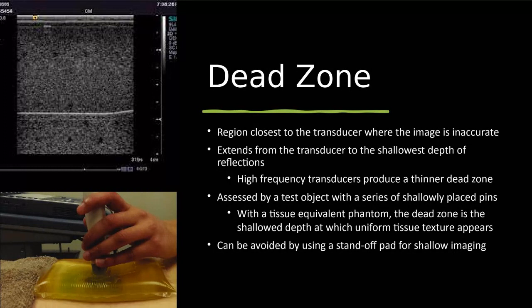So when they come in for QA, they are evaluating this. We want it to be as narrow as possible because we want as much clinically useful information on our picture as possible. So we said it's the region closest to the transducer. It extends from the transducer to the shallowest depth of the reflections. High frequency transducers are going to produce a thinner dead zone, right? Because they're better at evaluating superficial tissues. It's going to be tested with a series of shallowly placed pins in the tissue phantom. And then we'll be able to evaluate how the system can show those pins placed in that really shallow zone.